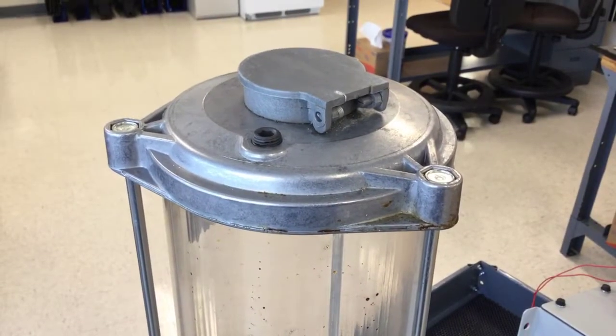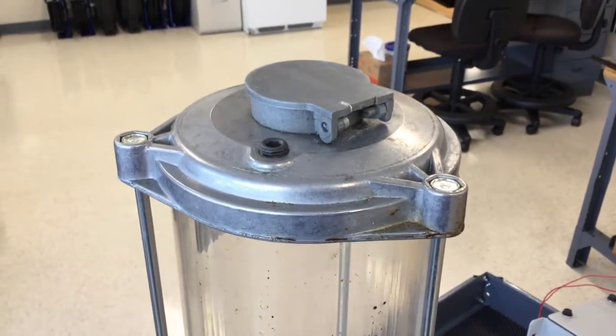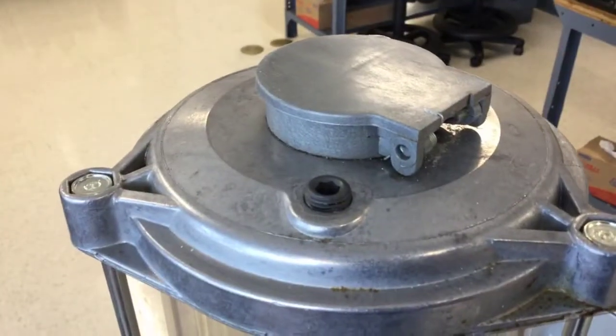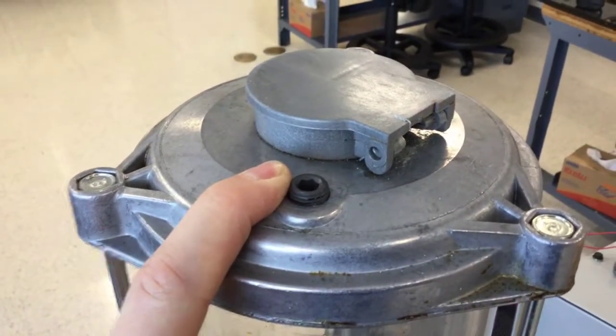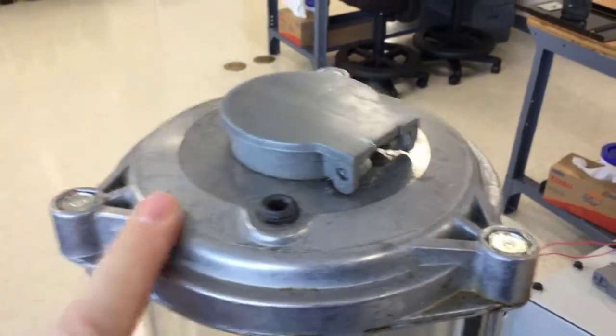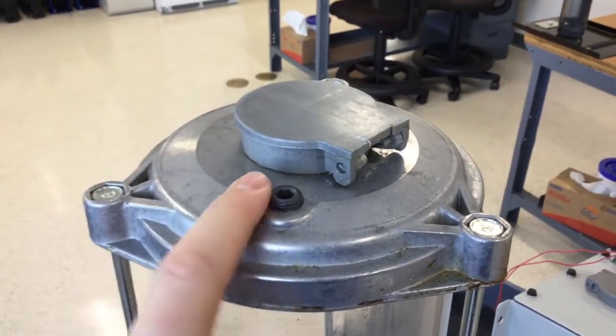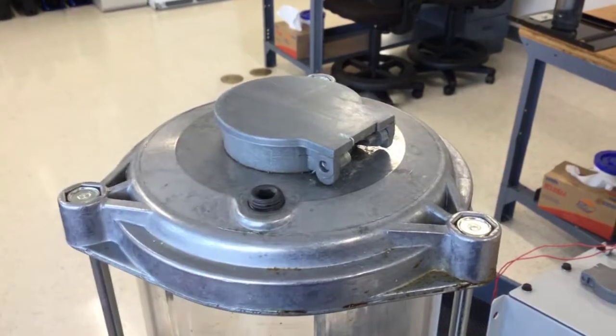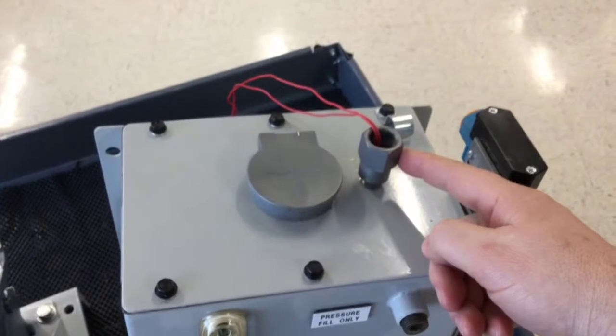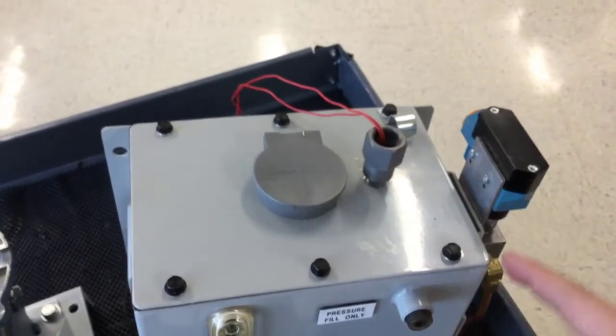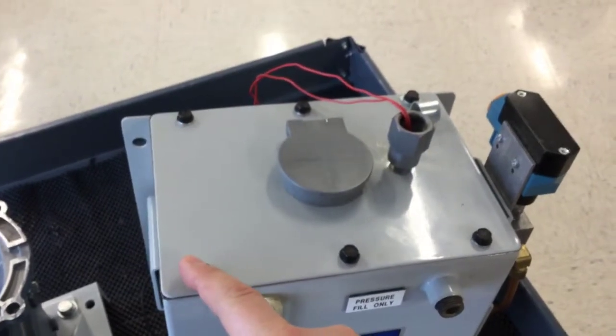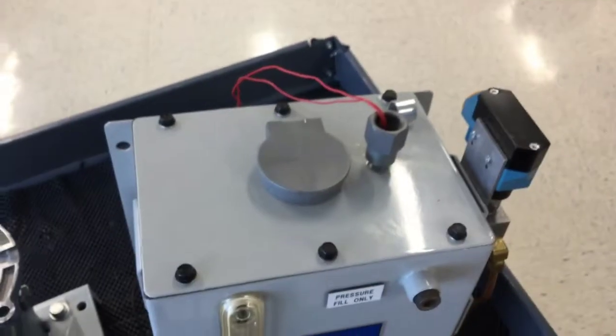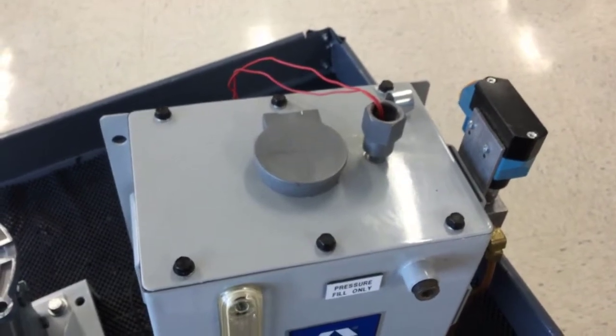Now when we install our oil low level switch, we're going to be looking at the top of the reservoir for this quarter inch pipe plug. In order to actually assemble the complete low level though, we're going to have to remove this whole cover and then we take the plug out and replace it with the switch assembly. It's the same for a tank. This one already has the low level switch installed over here, but this cover is easy enough to remove with just the six screws that hold the cover to the reservoir. Once that's off then you can pull the plug out and install the switch assembly.